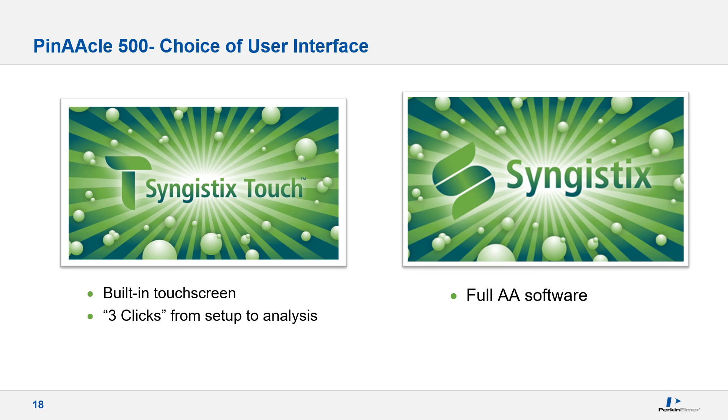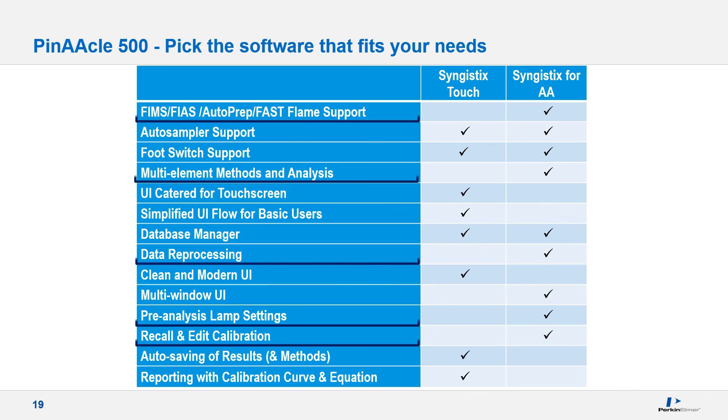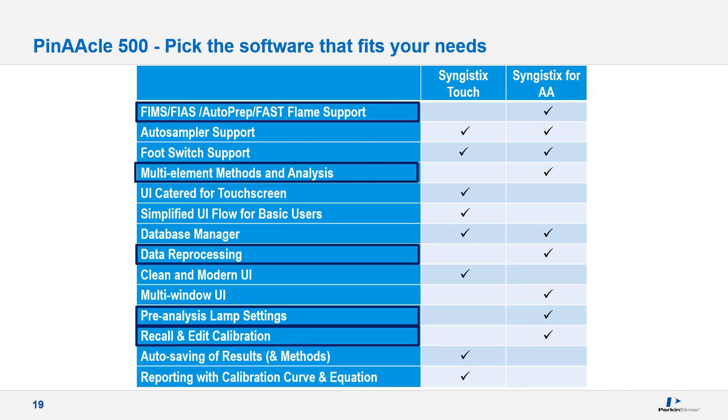There are two choices of software available for the PinAAcle 500: the touch version and the full Syngistix version. If you want to add FIAS or fast flame support, this requires the full version of Syngistix. Also, multi-element sequential analysis, data reprocessing, lamp preheating, and the ability to recall and edit calibrations all require the full version.